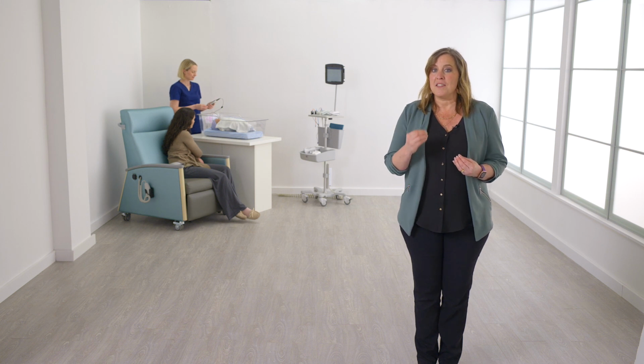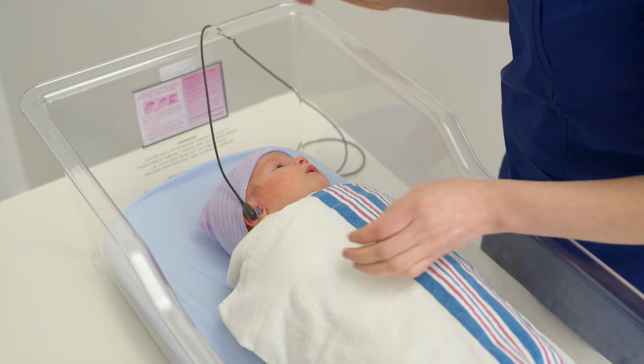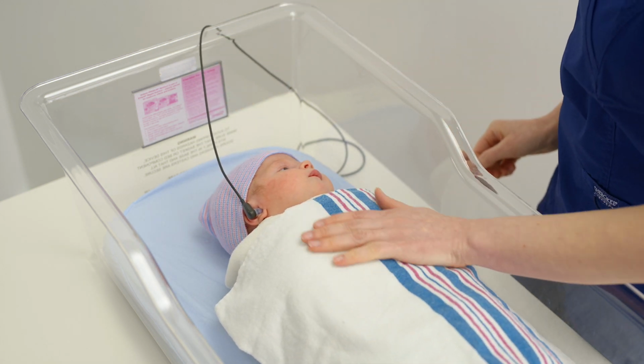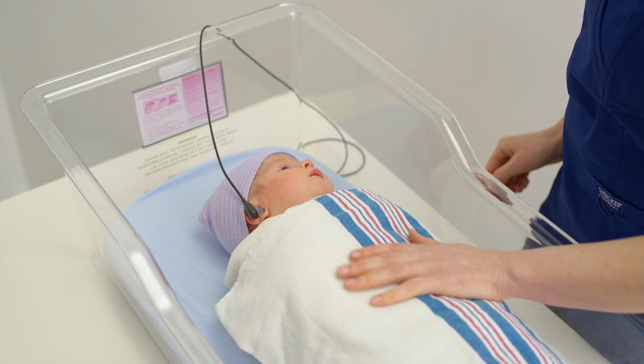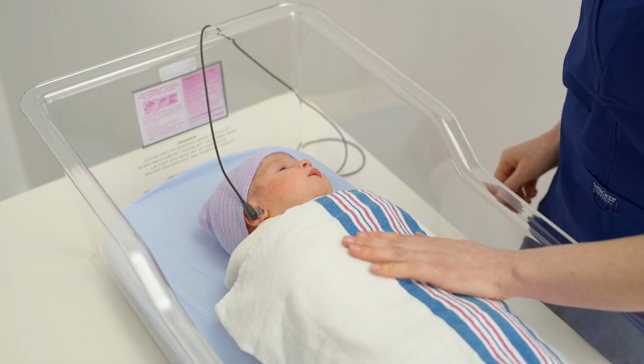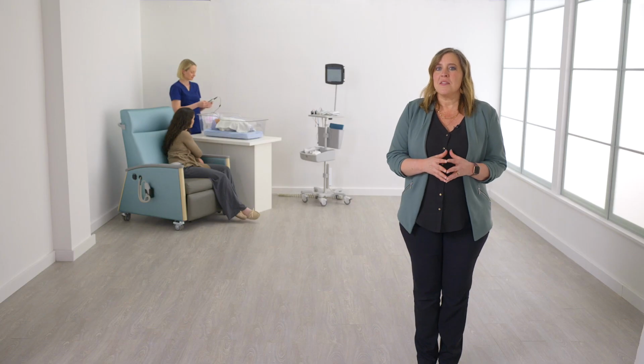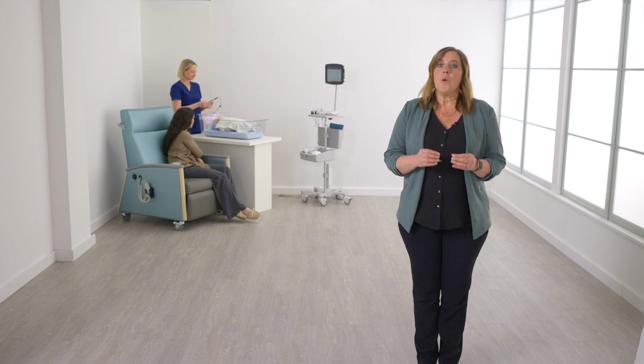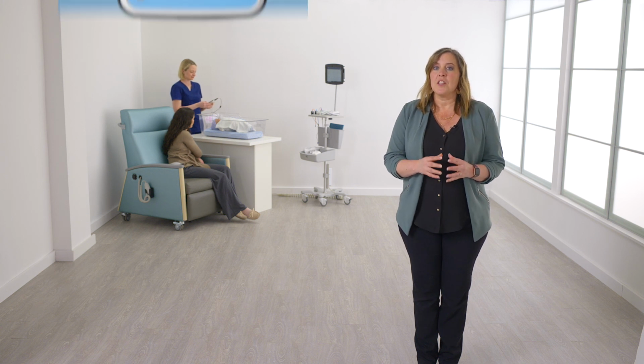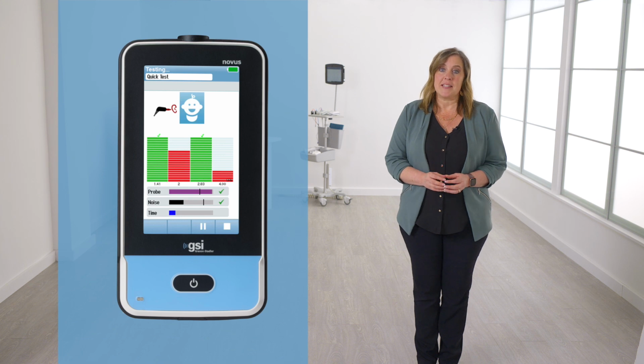If the probe fit is not acceptable, reinsert the probe tip, quiet the baby, and attend to any acoustic noises in the test environment if necessary. It is possible to stop the test at the probe check screen if adjustments are required. When the probe check is successful, the Novus will move automatically to the testing screen.